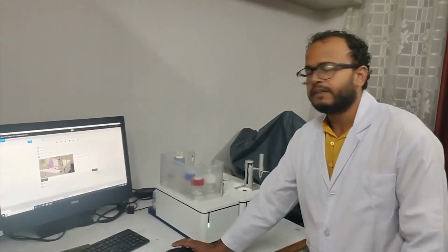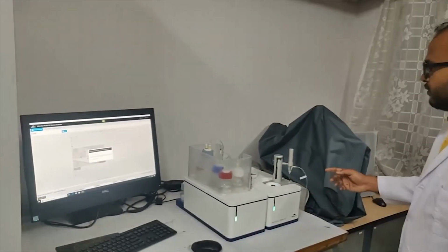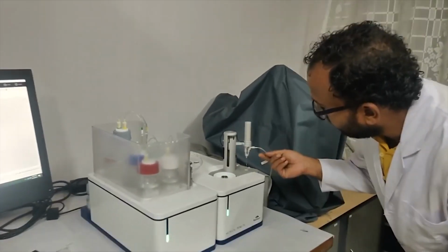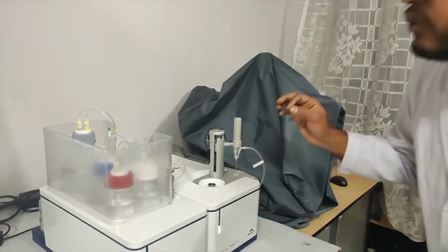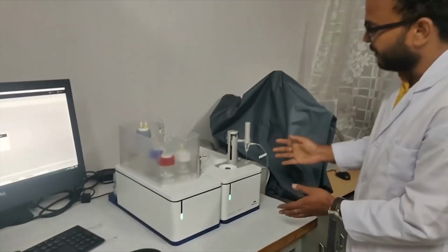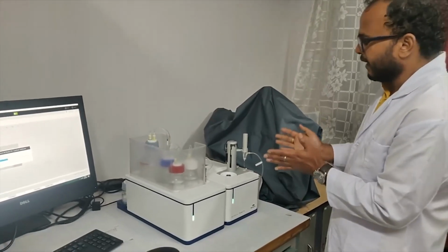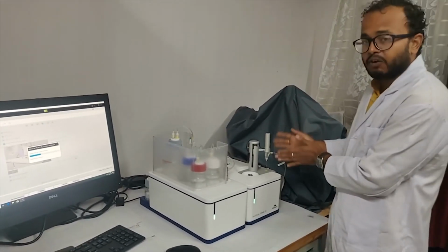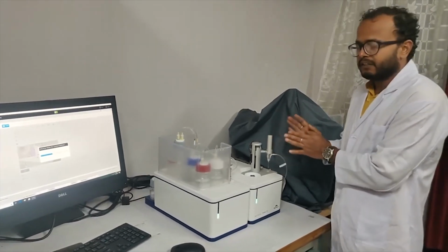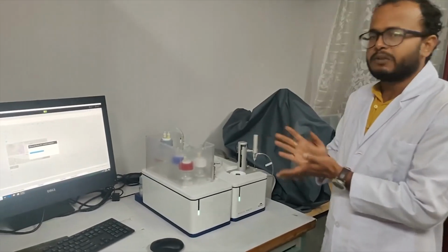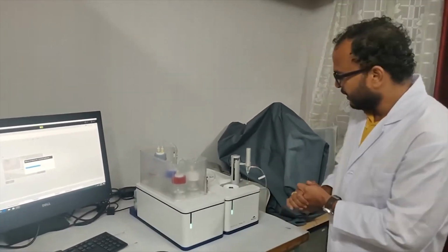So when we give the command from the software, it will start loading the ligand into the syringe. It will be in 3 steps. In the first step, it will open up the fill port, and after that it will remove whatever the dead volume is, and after that it will do purging and refilling. The purging is done by the instrument to remove any air bubbles in the ligand solution.